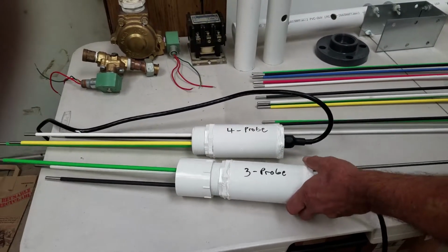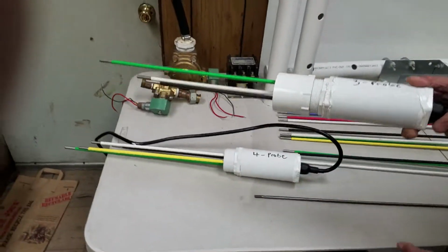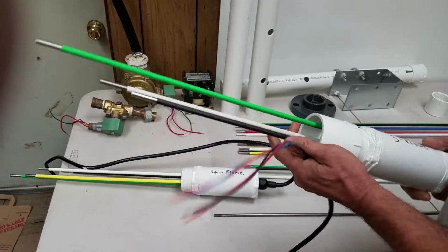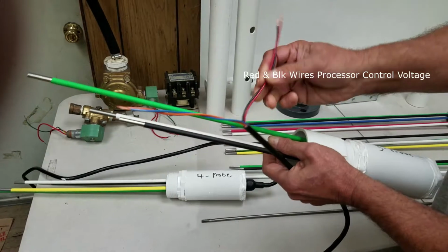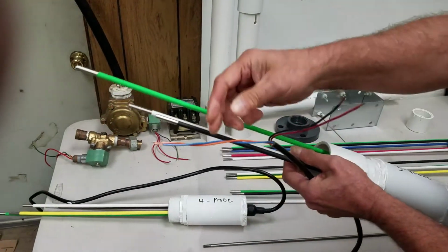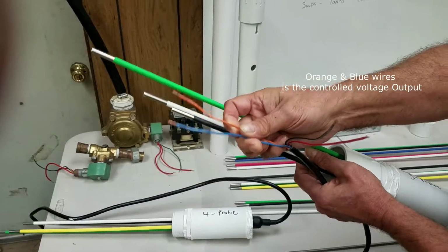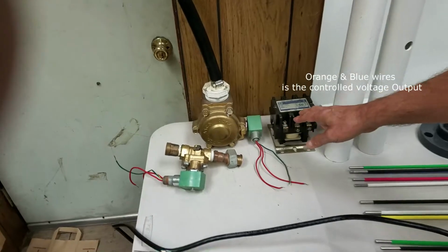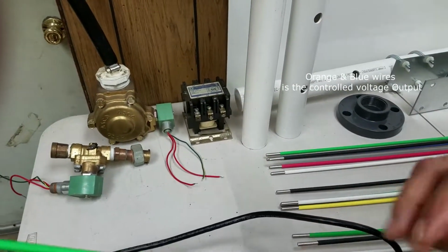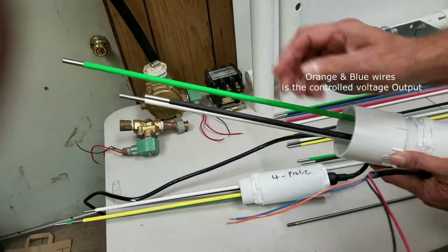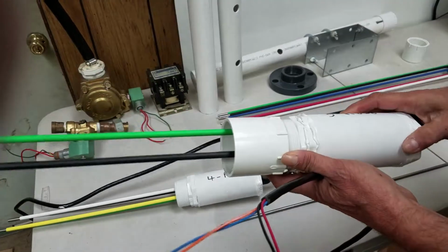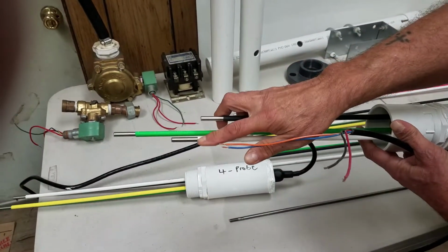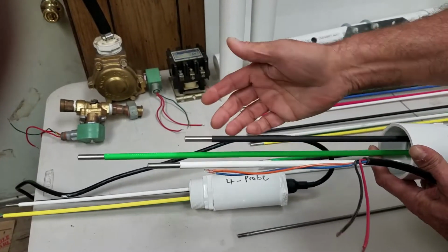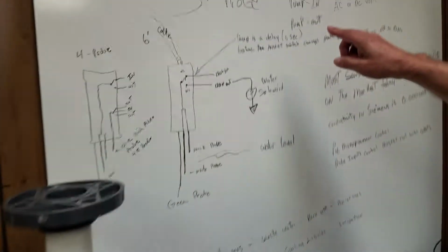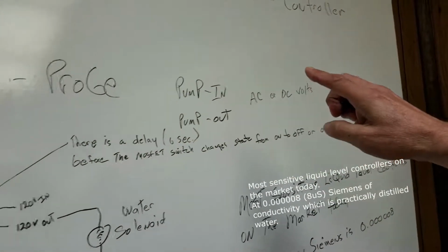Since the 3 probe is the basic probe, it's got 3 probes. This is your voltage, your control voltage for your electronics, and this is your controlled output for your solenoid, water solenoid, or a relay for a pump. You have these items as outputs. So your probes are your inputs. This is your outputs. This is a 3 probe, and it uses the black and white probe to control your water level, depending on whether you're using a pump in or a pump out, which needs to be determined before you purchase.